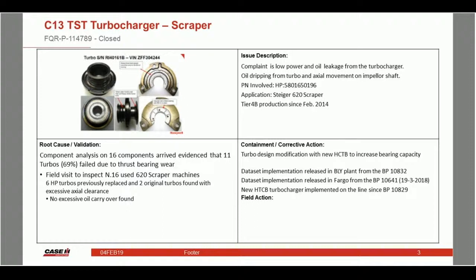Our investigation led us to the fact that at some conditions of load in transient, particularly on the scraper application, although you may see this elsewhere at times, caused the oil film to break down on the thrust bearing, and we had accelerated wear on that bearing.